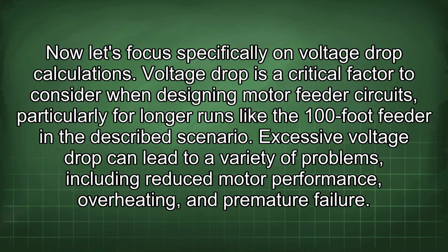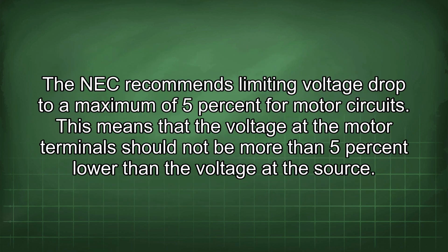Now let's focus specifically on voltage drop calculations. Voltage drop is a critical factor to consider when designing motor feeder circuits, particularly for longer runs like the 100-foot feeder in the described scenario. Excessive voltage drop can lead to a variety of problems, including reduced motor performance, overheating, and premature failure. The NEC recommends limiting voltage drop to a maximum of 5% for motor circuits.